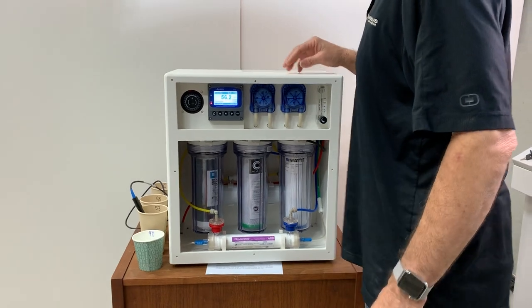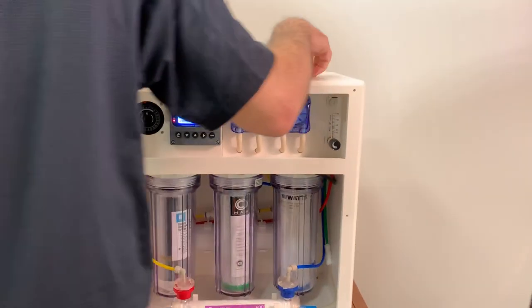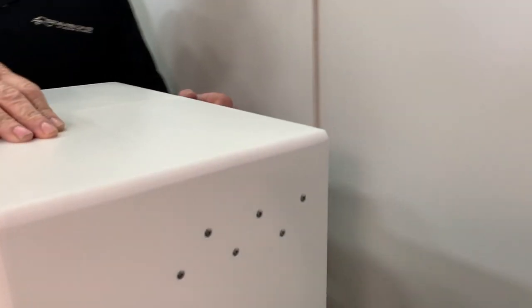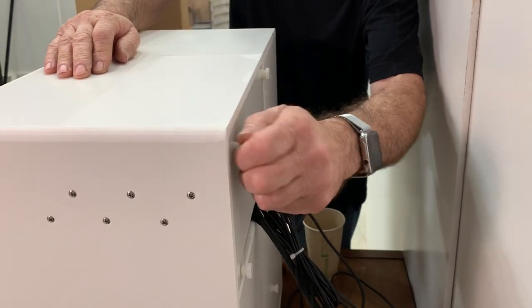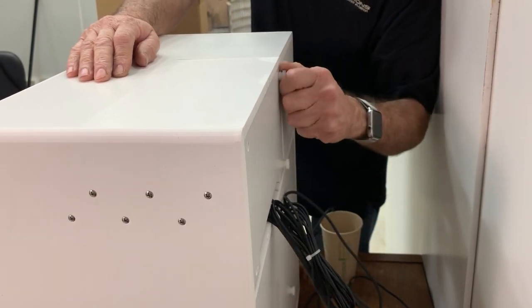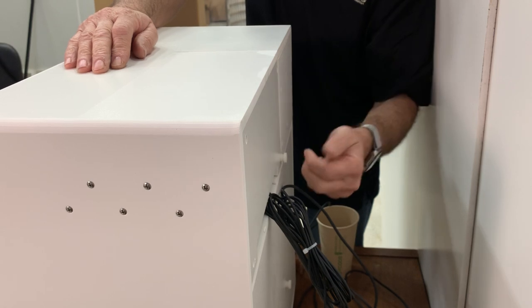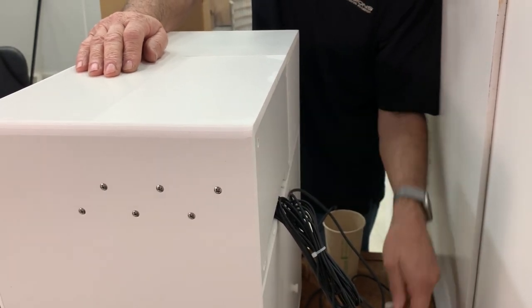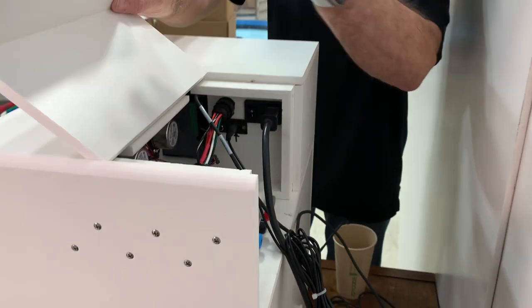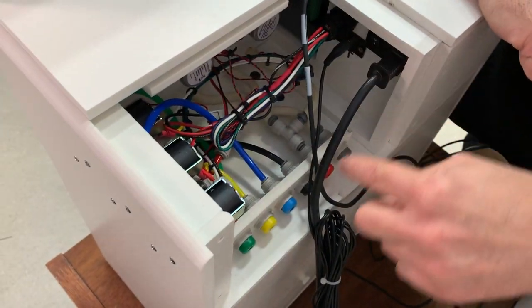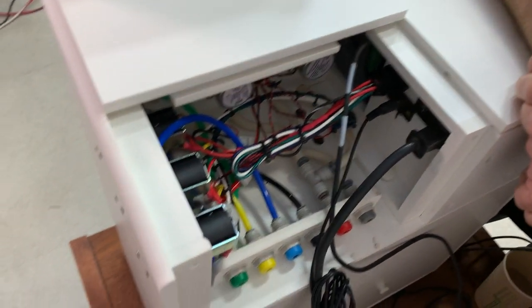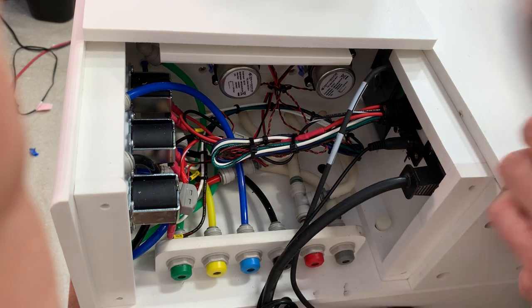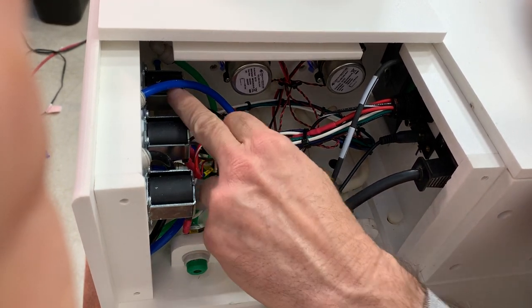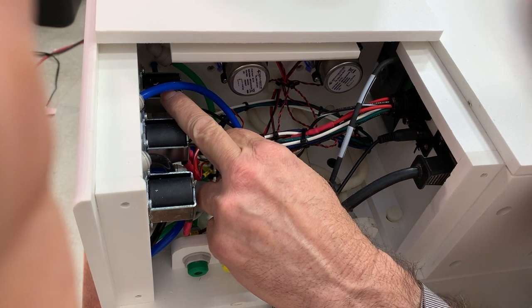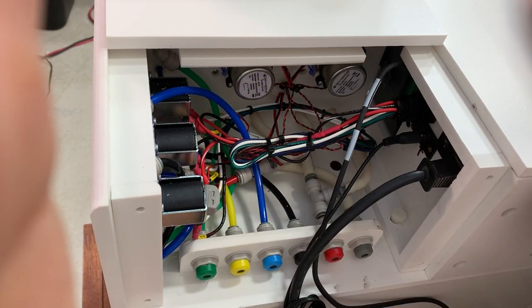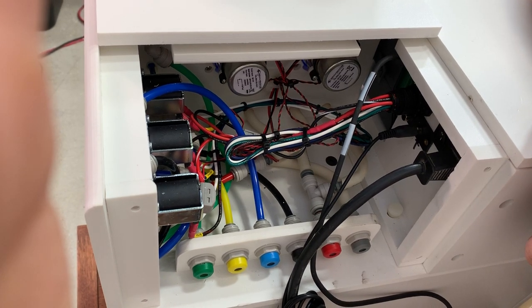So if you come around to this side over here, when you get your machine, there's a cover on the back. You take the thumb screws out, and you can just lift off this top. And you can see in here there's all kinds of electrical and plumbing all mixed together. There's solenoid valves here for your autofill, for your water valve, and there's another valve that sends water down to your dialyzer membrane when you're not autofilling.